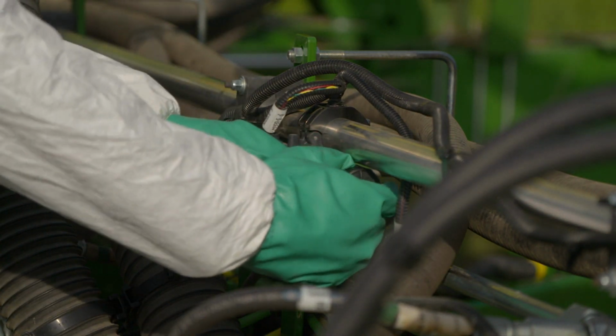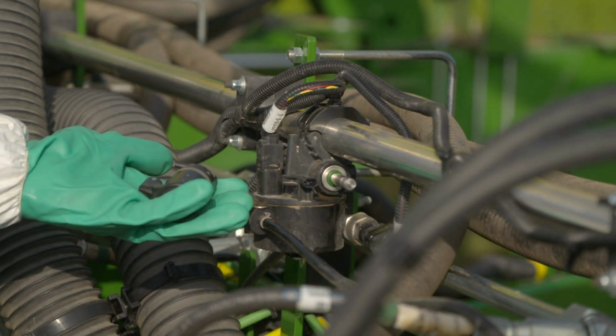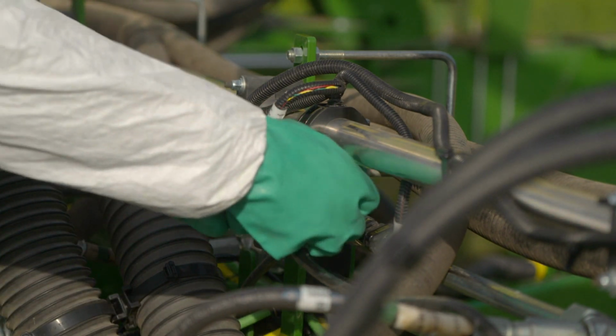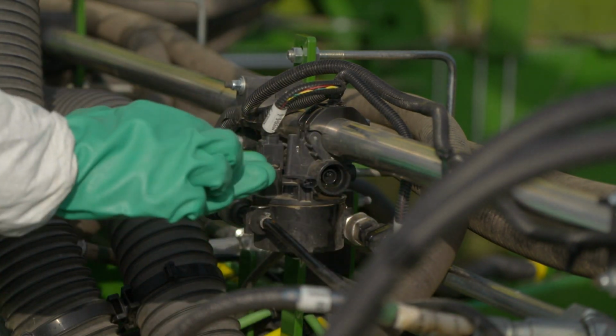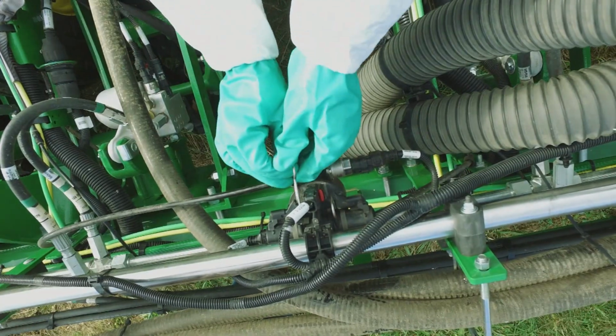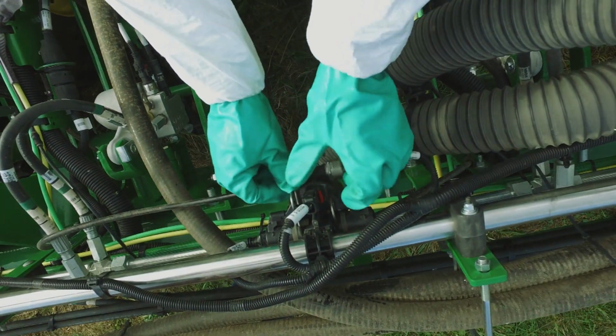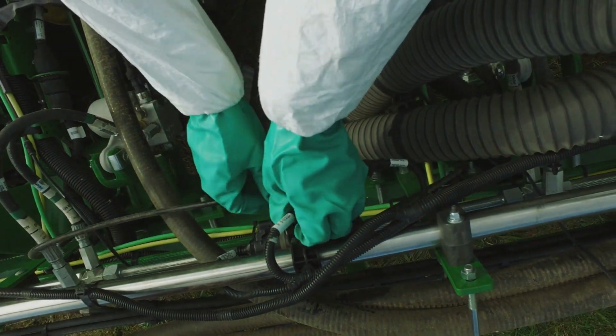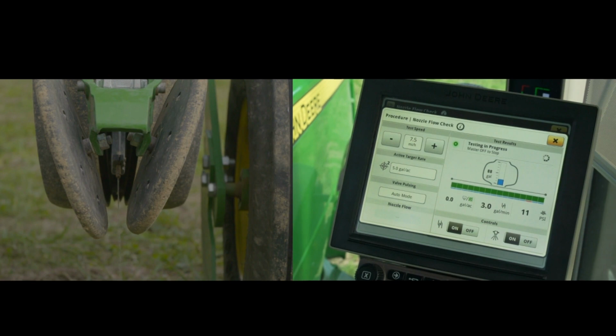Pull straight out on the solenoid coil. Pull straight out on the valve body. When reinstalling the valve, make sure the harness connection and retaining clip are properly seated. If a row gives a consistent flow warning even though liquid is coming out, then the sensor should be removed.